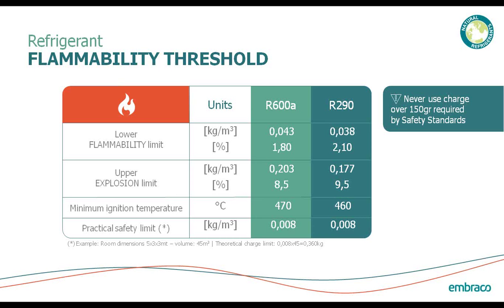These refrigerants' practical safety limit is about 8 grams per meter cubed. So if you have a 5 by 3 by 3 meter room — about 45 cubic meters — theoretically you're safe to charge that system up to 360 grams of refrigerant. But current IEC standards limit you to 150 grams without any special jurisdiction required. There are certain jurisdictions which will allow special permits to exceed these charges based on the type of occupants and volume of the room, but that requires special permitting. The point is that when you keep the charge limit down to 150 grams, you're looking at a fairly safe system.